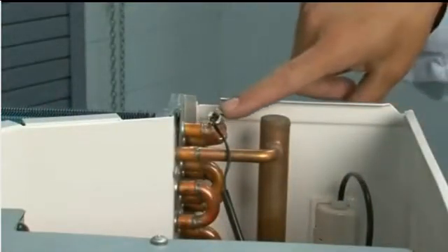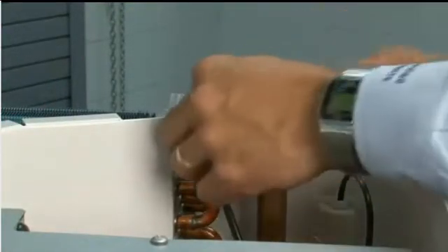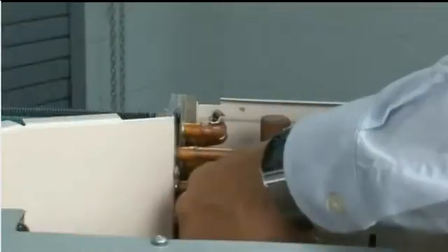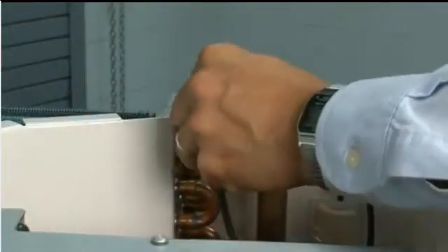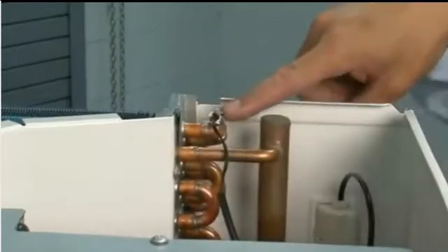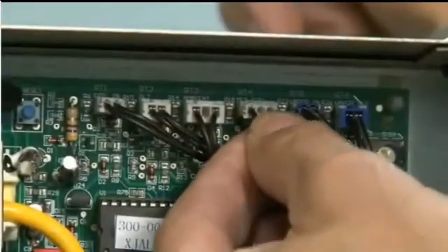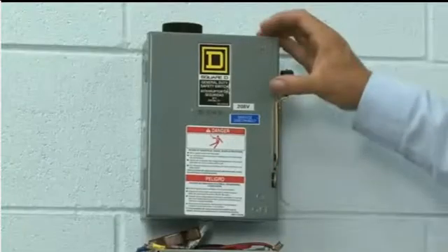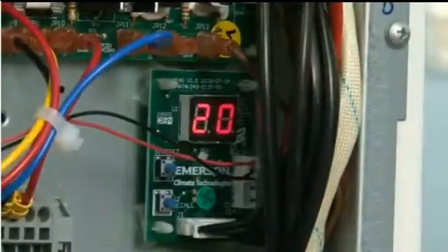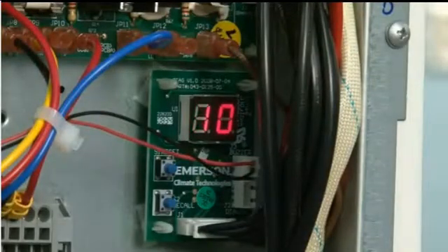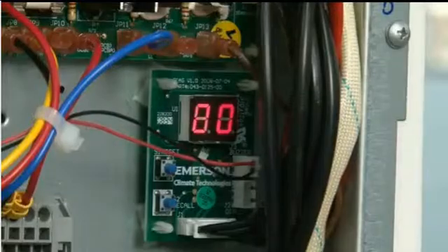Find the sensor within the well and remove it. Pull the cable out of the system and replace it with a new one. Attach the new sensor in the well and to the main control board. When you reattach power to the unit, it will again go through the fresh start sequence. When the fresh start has completed, the error code will be cleared and the display should read 00, meaning the compressor is off.